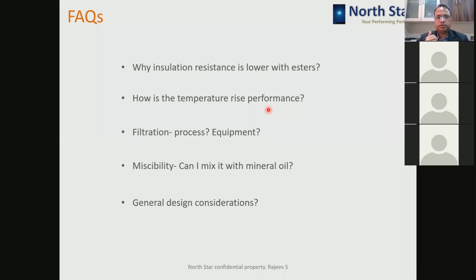Synthetic, mineral, and natural ester are miscible with each other, but at the cost of their individual properties. Suppose you mix mineral oil into the natural or synthetic ester, then the biodegradability will get questioned. Fire safety, flash point will come down, so it will not give you that good fire performance. Overloading capability will come down because moisture absorption capacity will get compromised.